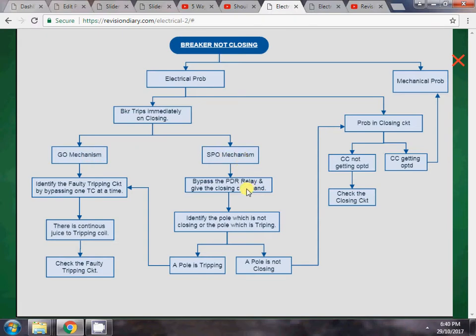For a single pole operating mechanism, there is a PDR relay which trips the breaker when it senses a difference in the closing or opening time across the three poles. We will bypass the PDR relay by removing the positive or negative supply to the coil of the PDR relay, then give the closing command. This way we can identify which pole is not closing or which pole is tripping.